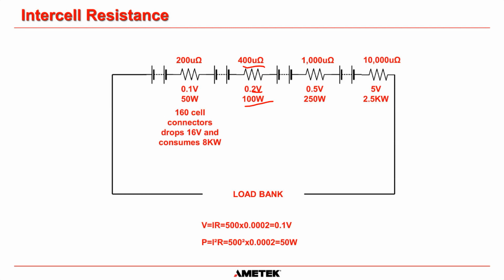And then if we go even further and the intercell connections are 10,000 microohms higher, maybe they haven't been torqued correctly, maybe it's in a very dirty environment and they're corrosive, then there's going to be 5 volts dropped across each intercell resistance. 2.5 kilowatts dropped across each resistance. That's a huge amount of power. That's going to cause these connections to heat up and even start to melt.